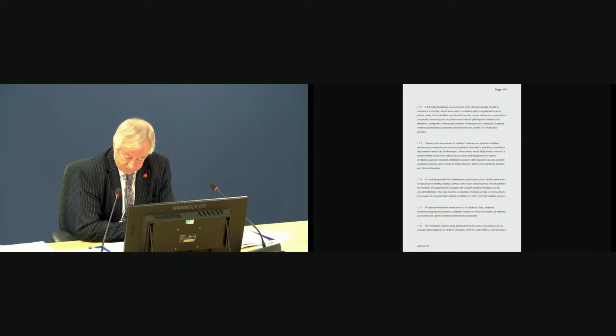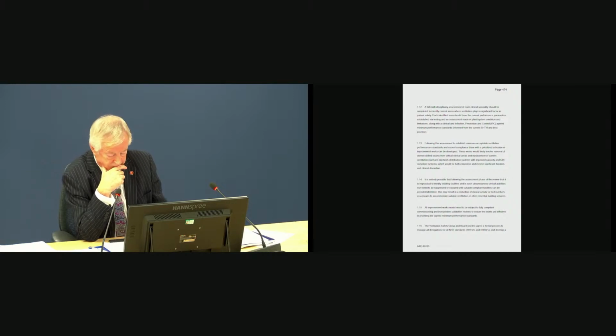This is where it becomes a technical assessment to simply increase the air change rate within the room. It relates directly to the sizing of the ventilation ductwork and the velocity at which air travels through it, noise transmission, drafts and comfort factors for patients, not to mention that you cannot operate chilled beams at the increased ventilation rate of 6 air changes an hour for a general ward area. So it is not straightforward—you can't just pull it out and turn the fan up, as you say.